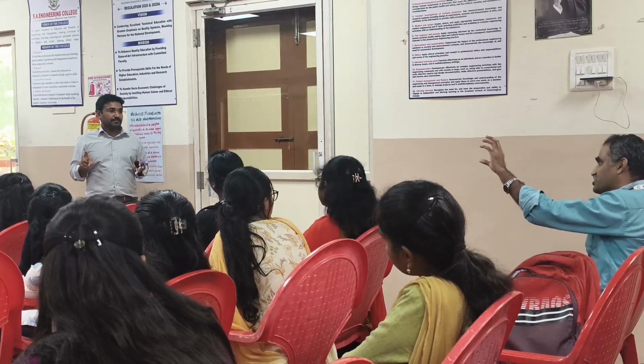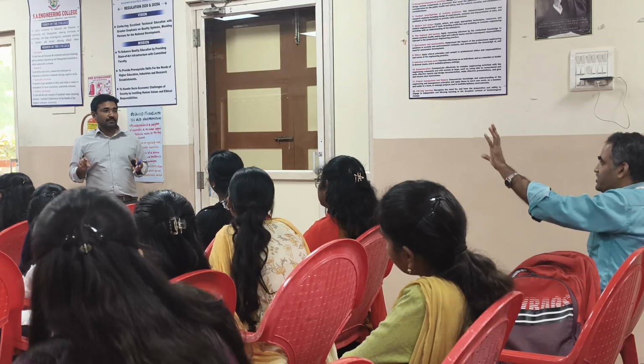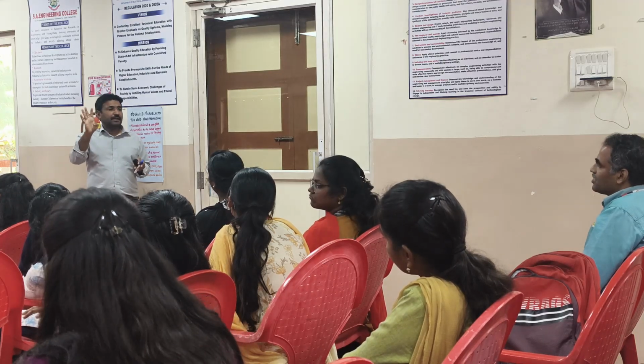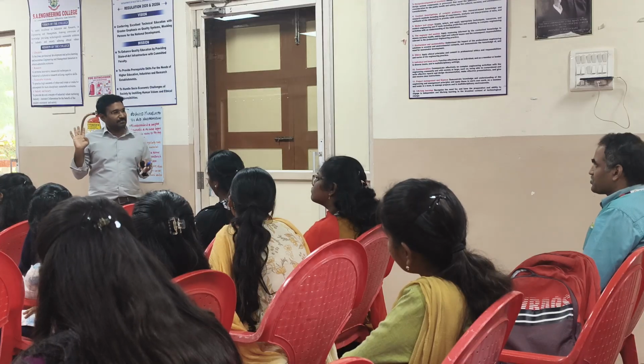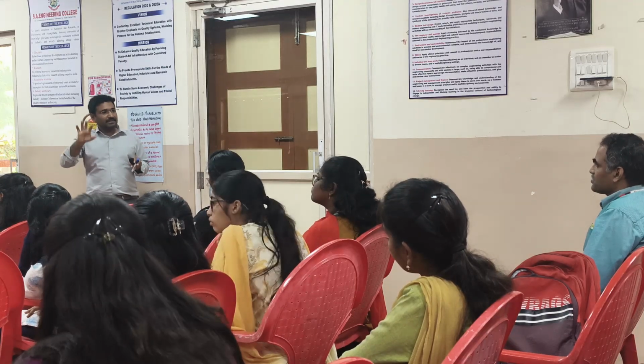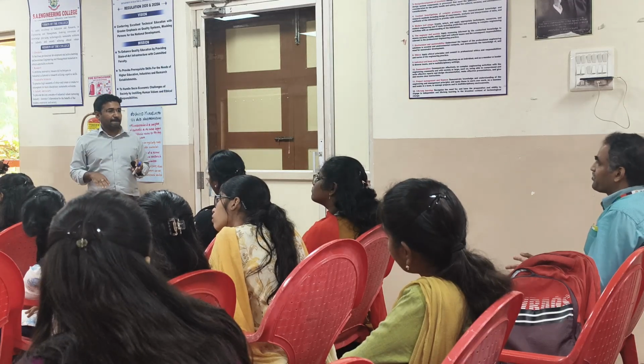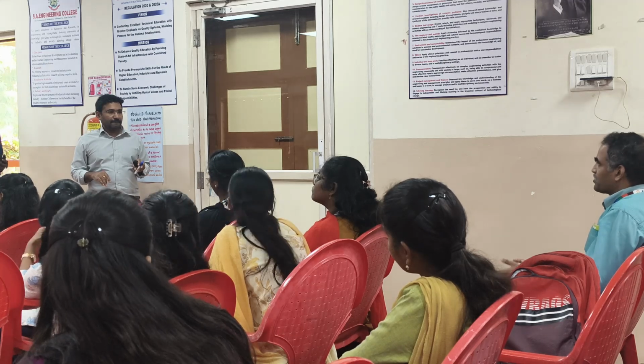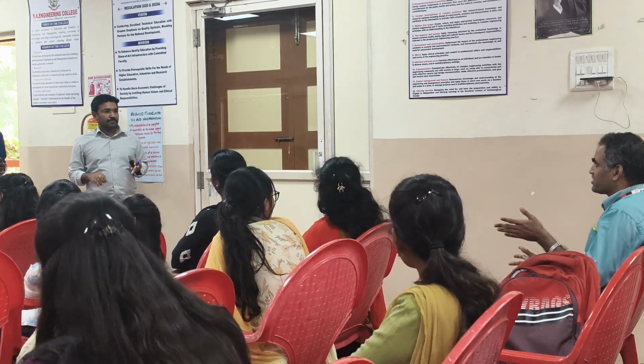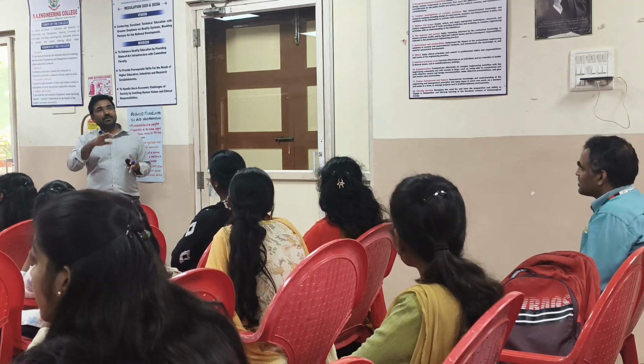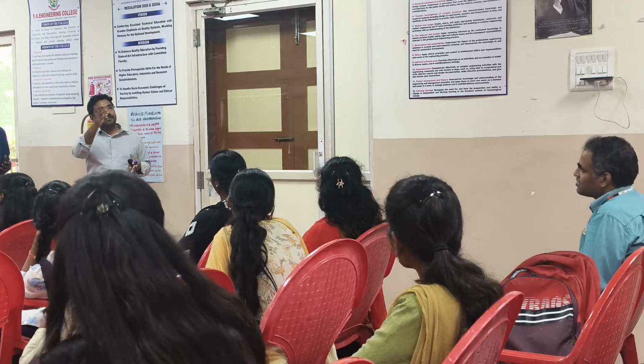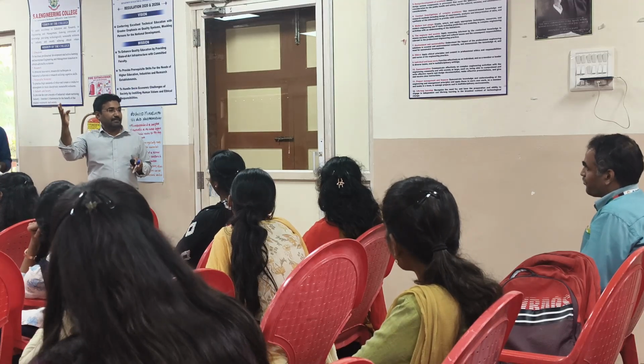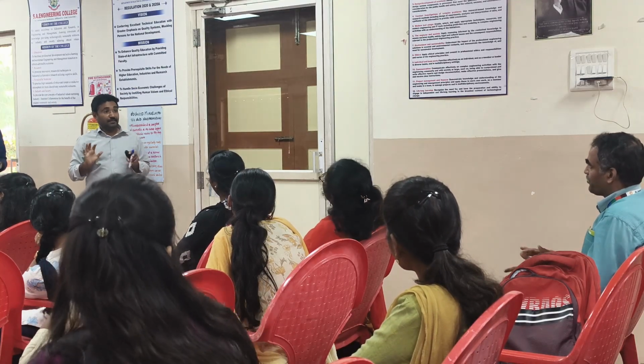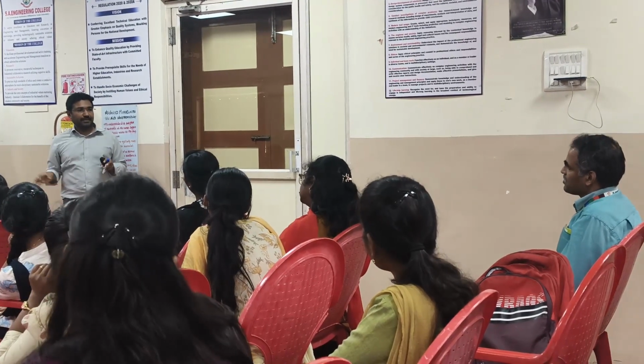Is that a specific frequency? Of 3% to 5% is accepted. So whenever we design the inverter, we maintain it. It's not that kind of fluctuation because normally even that is not there. So we consider the fluctuation, the grid fluctuation also. If you look at the frequency, 49.2 to 50.5 is the allowed frequency. Even the allowed frequency, it is not an issue there.